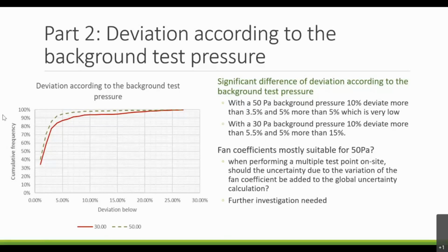And we found out that with a 50 Pascal background pressure, 10% deviate by more than 3.5%, and 5% of the fans deviate by more than 5%, which is very, very low. But for the certificates with a 30 Pascal background pressure, we have a much higher deviation, with 10% deviating by more than 5.5% and 5% by more than 15%. So it seems that the fan's coefficients are mostly suitable for 50 Pascal, and so when performing a multiple test on site, maybe there is also an additional uncertainty due to the variation of those coefficients with the background pressure, and that shall be included in the global uncertainty. So we really need to have further investigation on this subject.